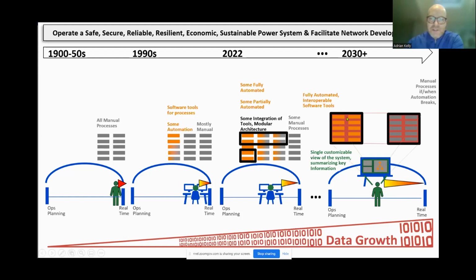And this dashboard is taking information from the automated processes, which are the orange blocks here, and they're fed by the red behind, which indicates data, network, and models. These automatic processes have to have a link to the backup manual processes because automation will break. So when it breaks, the operator has to be able to intervene and go for a manual fix of it. And finally, the last step in the process is that all of these are linked to a simulator environment or operations readiness environment where your processes, tools and systems are all replicated in a digital twin simulator type environment. You have high performance simulator capability here, and this is a triangle where your processes are replicated across the three environments.